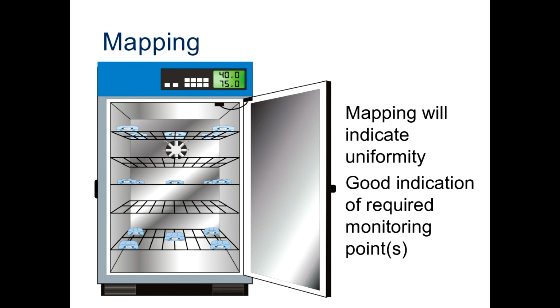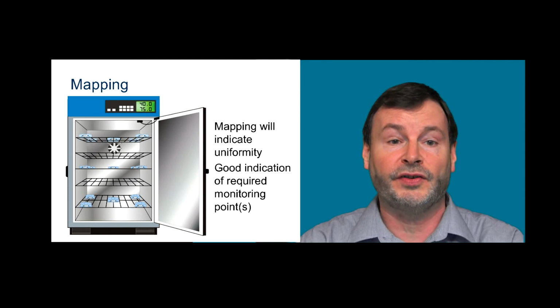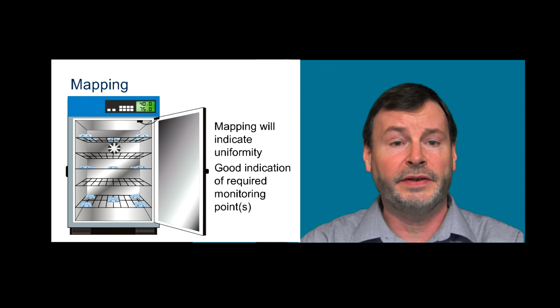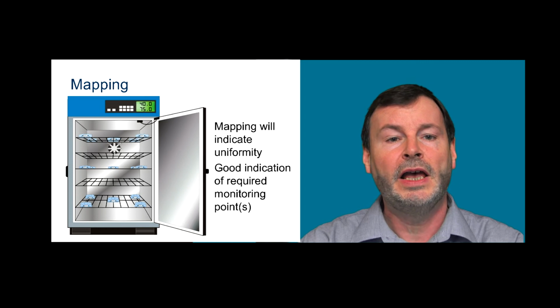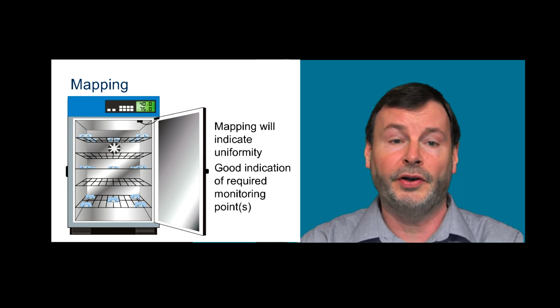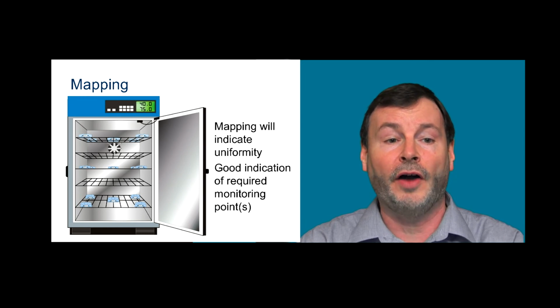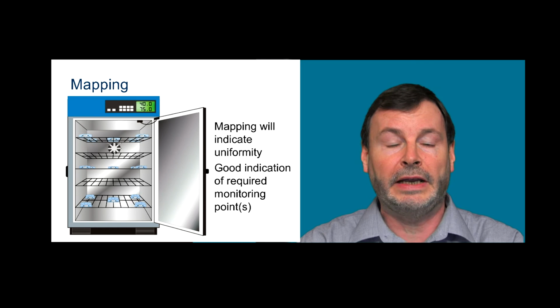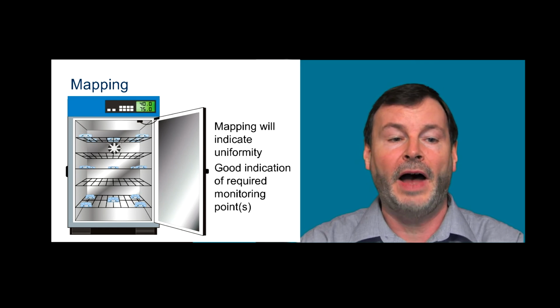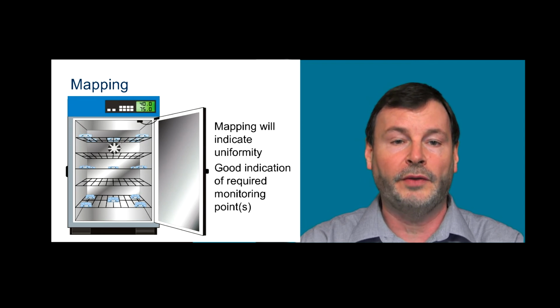Now, in the case of a chamber where the conditions may be much tighter, in this case, we have a stability chamber, which will be operating at 40 degrees C and 75% RH. Now, at that value, just a 0.5 degrees C temperature change will induce a 2% humidity gradient. And now if we add any sort of measurement uncertainty from the instrument, we can easily be at 4 to 5% humidity, which is what we're trying to control to in the first place. So in this case, in a stability chamber, mapping it is probably a good idea. In this example, we've shown mapping on 3 shelves, top, middle, and bottom, with 5 monitors on each shelf for a total of 15. That would really give you a good idea of how many monitoring points are required if you've got good uniformity throughout the chamber.